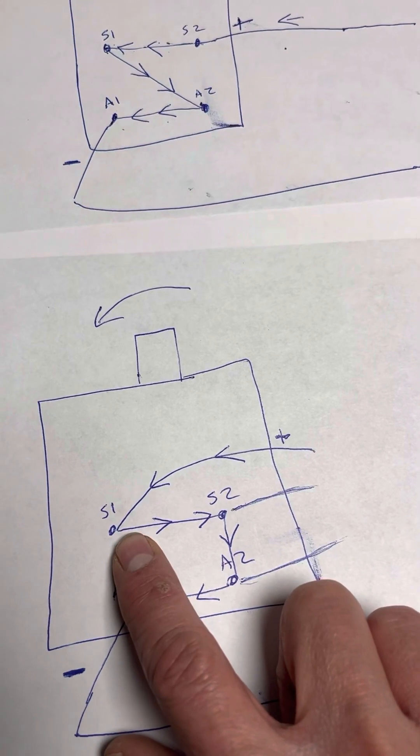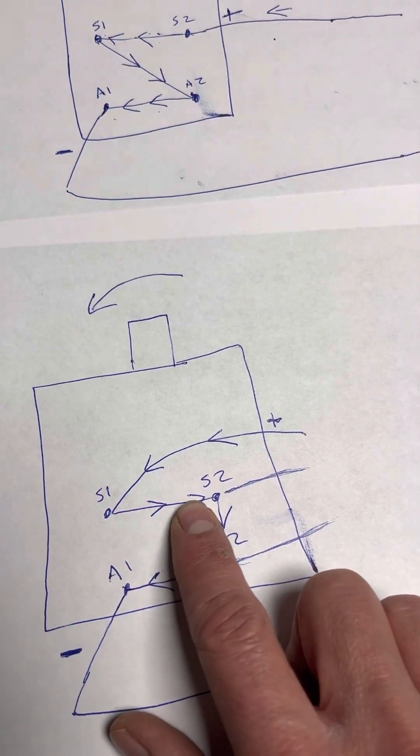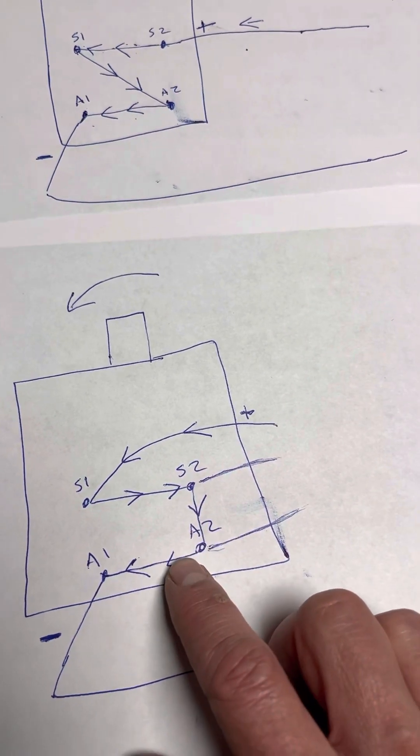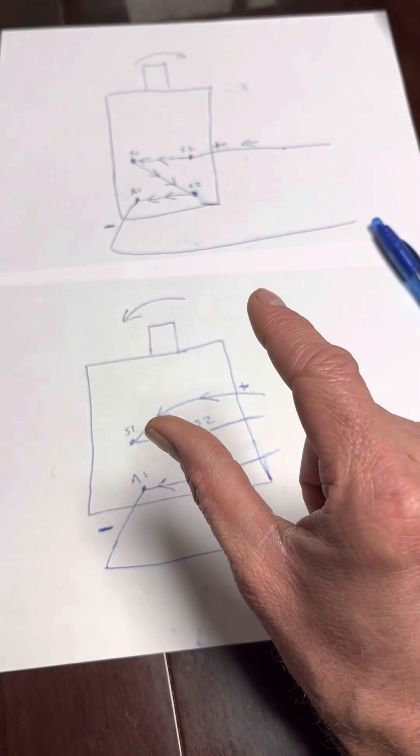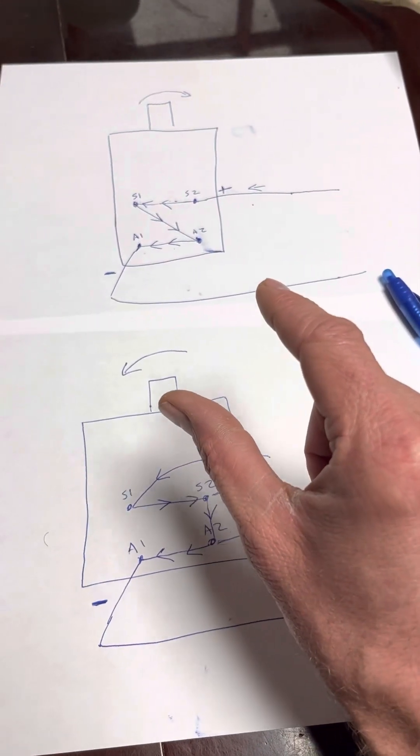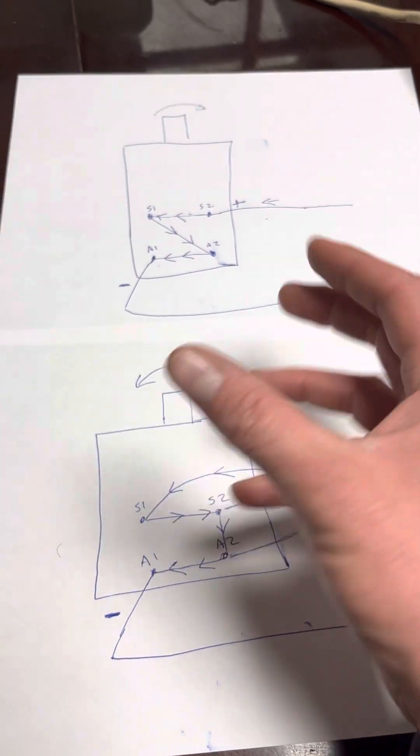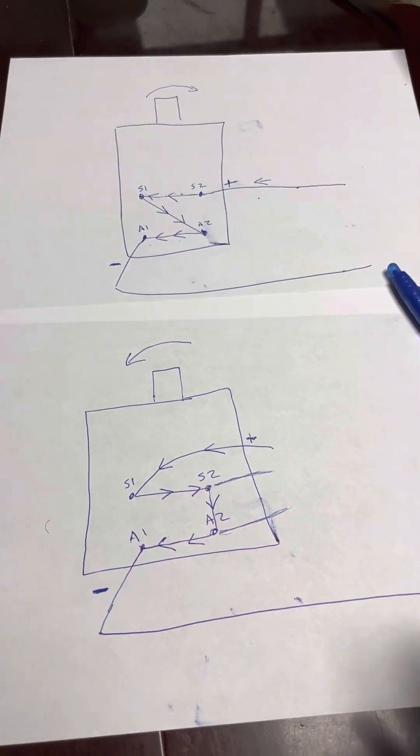What you have is the current flowing through the stator this way, and then the current flowing through the armature that way. So you have to switch the polarity of the fields to get these motors to spin the other way.